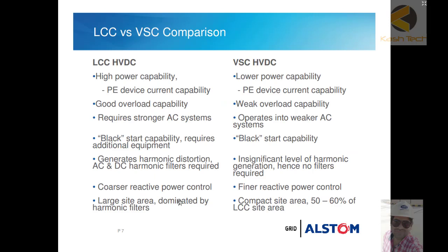So again we can have another comparison. LCC has high power capability and PE device current capability, whereas VSC HVDC has lower power capability and PE device current capability. LCCs have good overload capacity, VSCs have weak overload capacity. LCC requires a stronger AC system, VSC operates into a weaker AC system. LCC HVDC black start capability requires additional equipment, whereas black start capability does not require additional equipment in VSC HVDC.